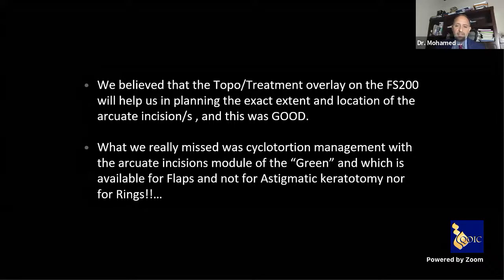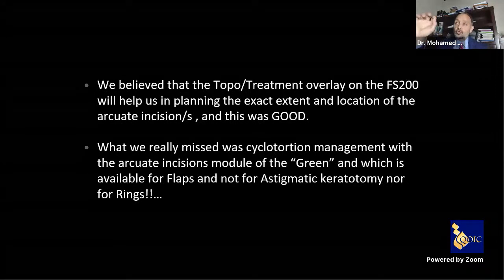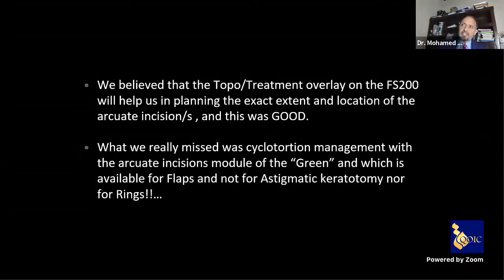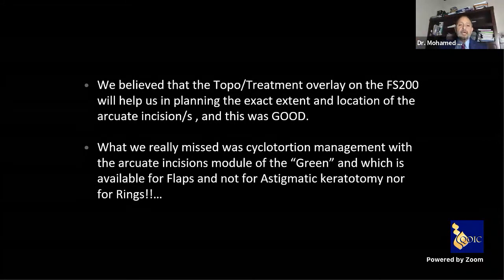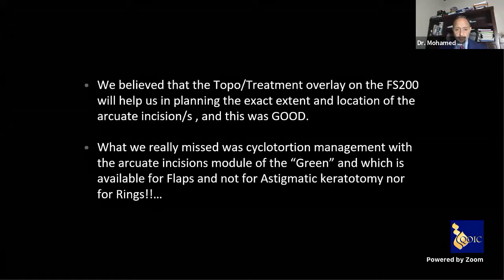Using the overlay, you can rotate the arcuate incisions on the screen until they are exactly on the scarred area — rather than just typing in the axis numerically. For example, you might plan 60 degrees but the overlay shows you need 64 or 68 degrees. This is a very handy tool when using femtosecond laser for arcuate incisions.